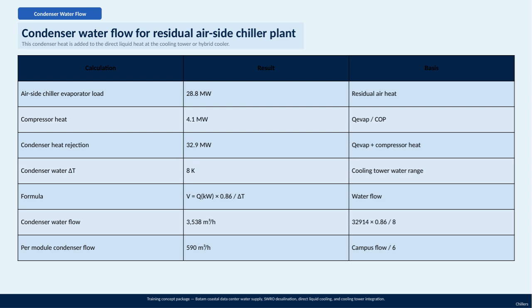Looking at the table, the airside chiller evaporator load is 28.8 megawatts, which represents the residual air heat being removed. The compressor contributes an additional 4.1 megawatts of heat based on the ratio of evaporator load to the coefficient of performance, or COP. Adding these together gives us the total condenser heat rejection of 32.9 megawatts. The condenser water temperature rises by 8 Kelvin across the cooling tower, which is our delta T, or temperature difference. Using the formula shown, where water flow volume equals the heat load multiplied by 0.86 divided by delta T, we calculate the condenser water flow rate to be about 3,538 cubic meters per hour.